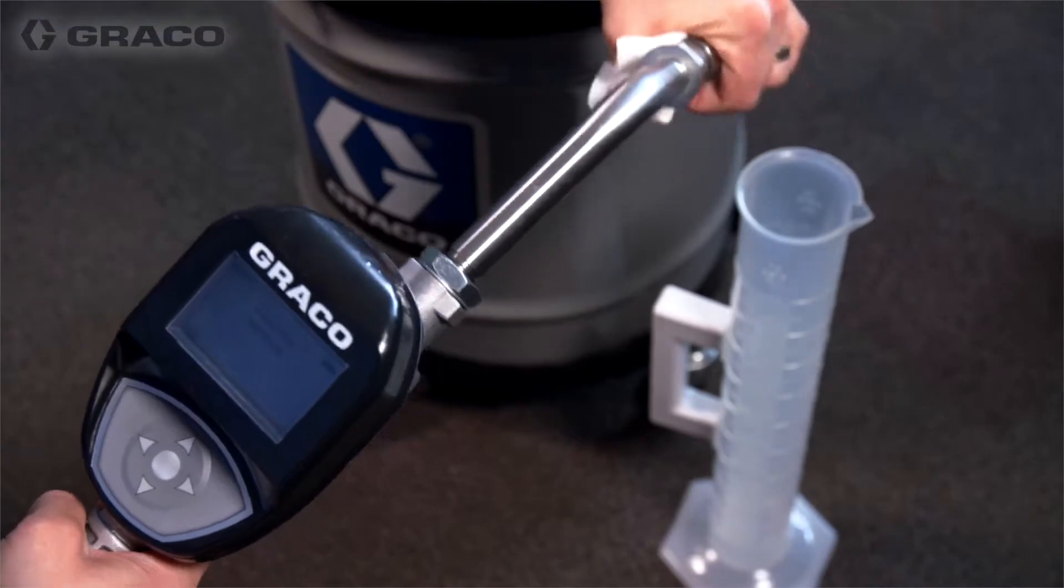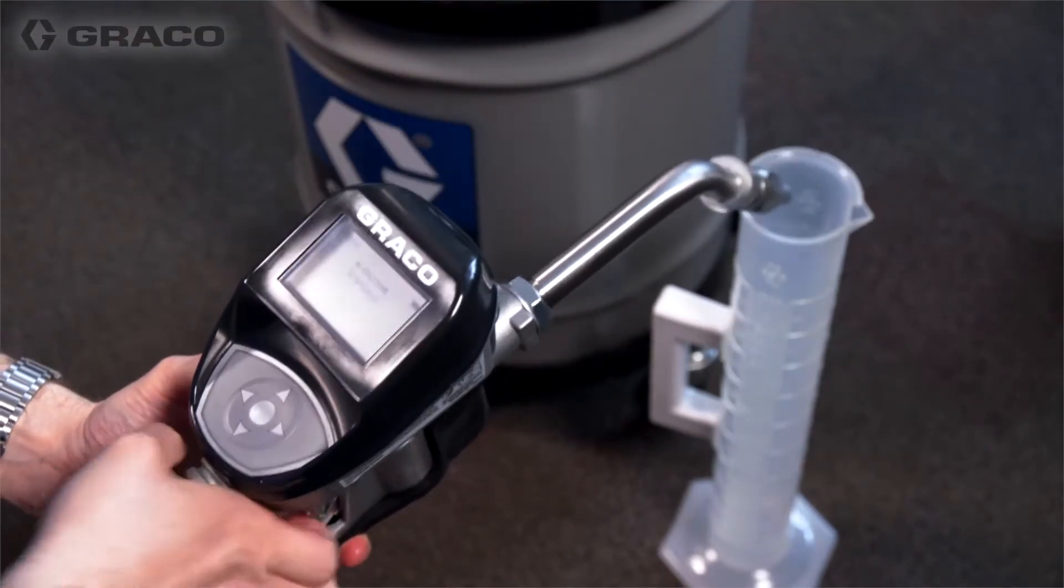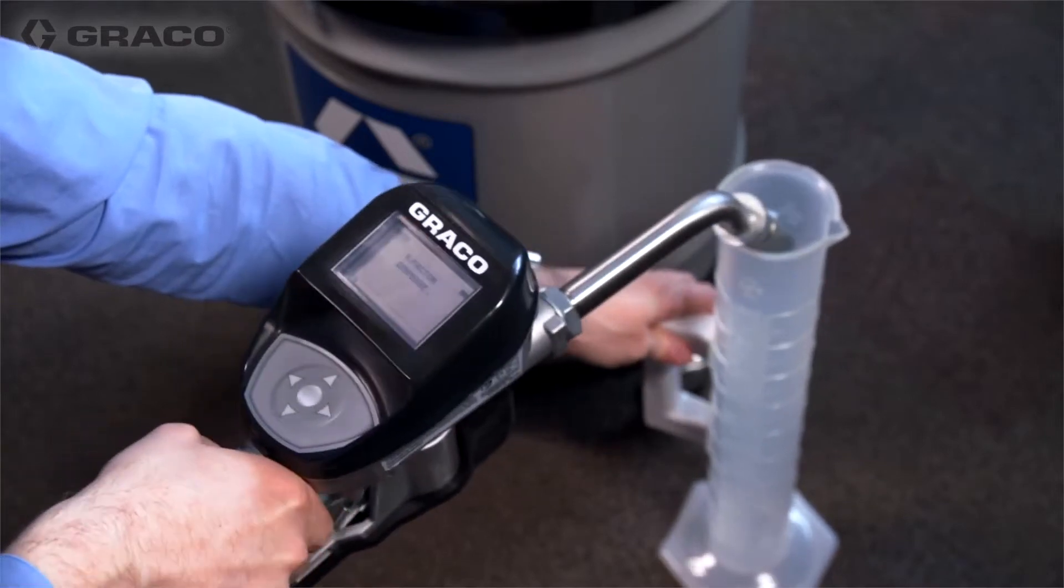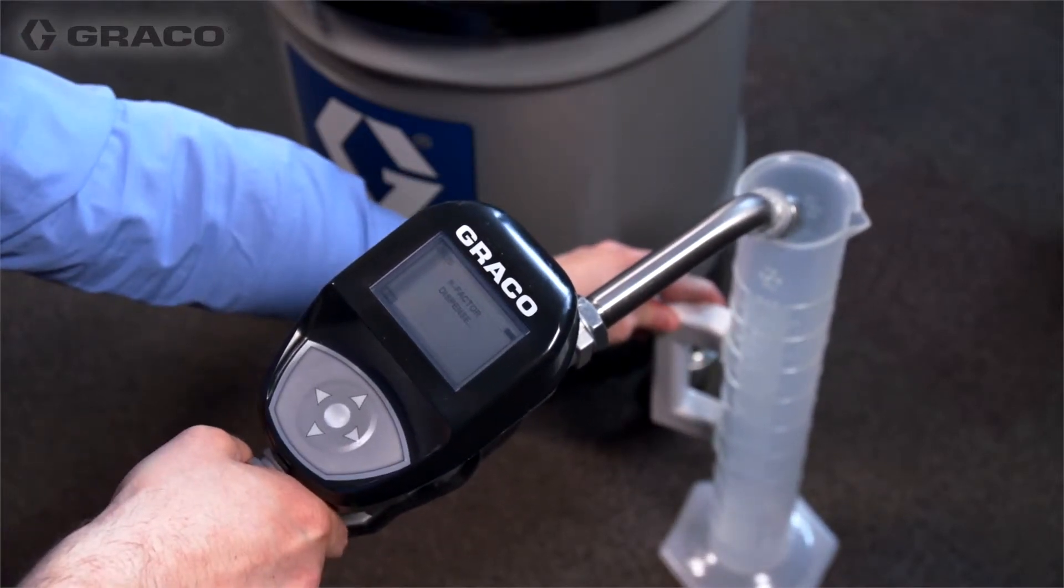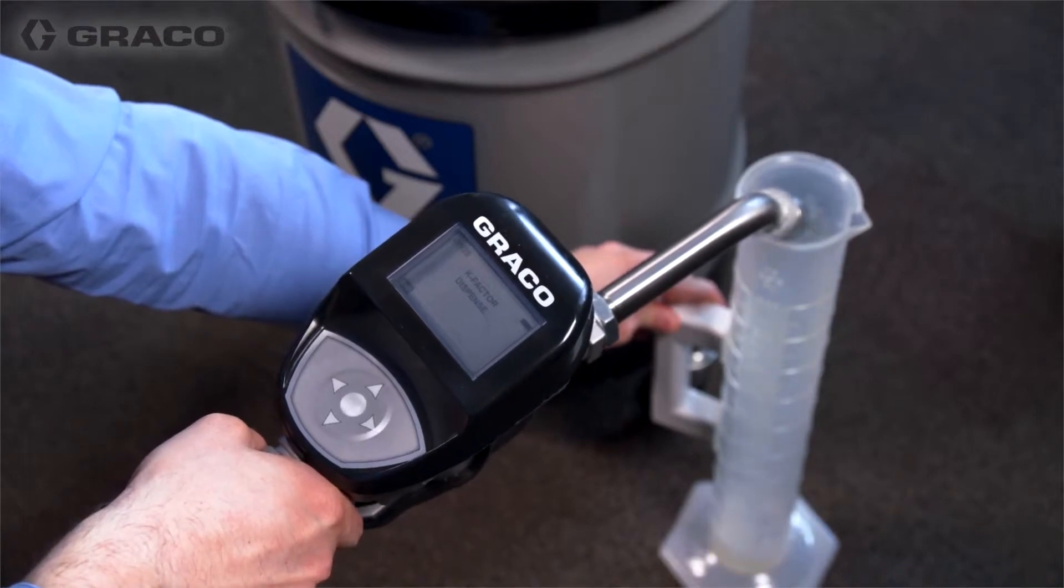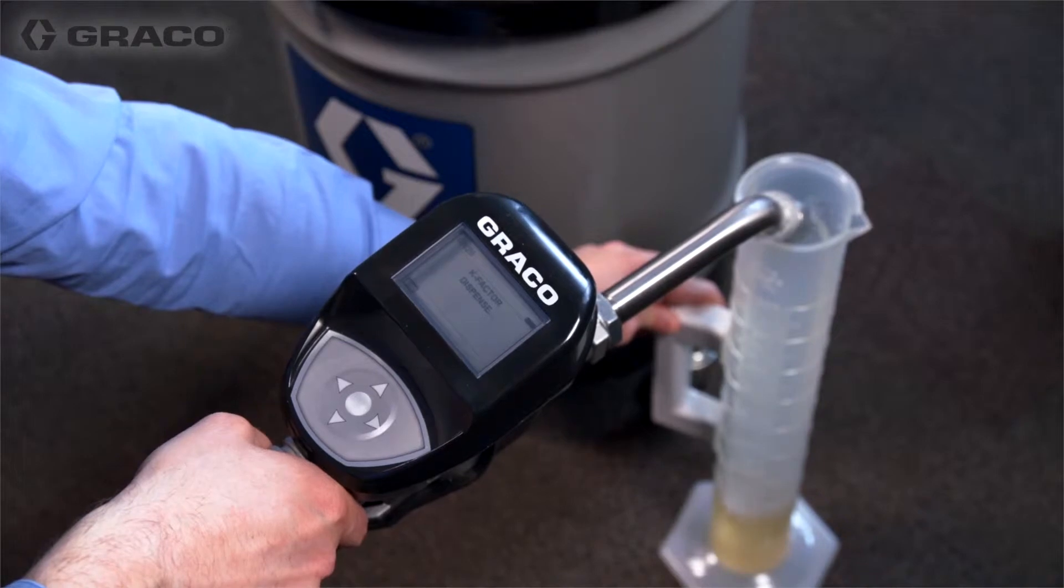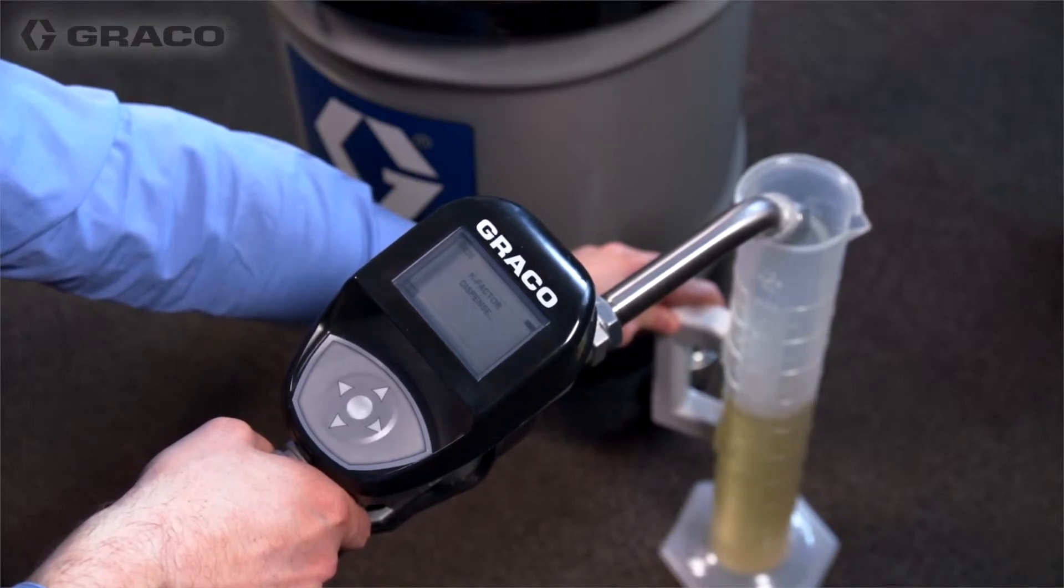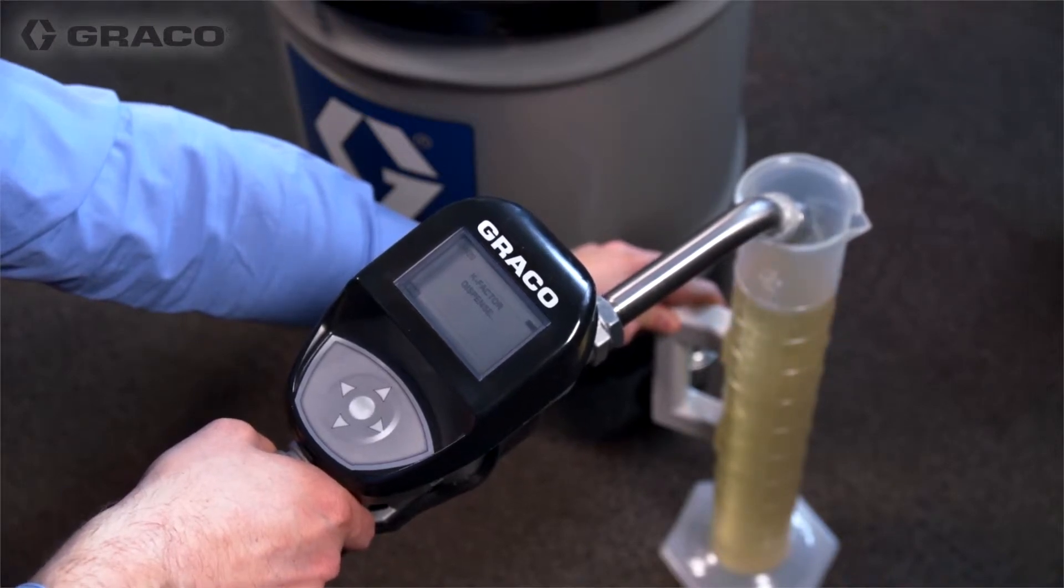Dispense exactly one quart or one liter of fluid into a one quart or one liter clean calibrated volumetric container. The units you choose depends on which units your meter is set for. Ensure you are using the same flow rate as in normal operation. Note, during the calibration dispense, the meter will not display the volume dispensed. The volume dispensed is only determined by the container measurement.